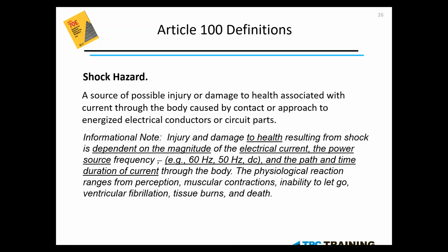Now, shock hazard, other than arc being the heat hazard, now we have the shock hazard, is a source of possible injury or damage to health associated with current that flows through the body by either contact or approach to energized electrical conductors or circuit parts. This is a very serious subject. More times than not, when people think of 70E or electrical safety, they think of the flashes and the blasts because they are visually out there, but 98% of all fatalities come from the shock hazard. So we need to also stress the point of keeping our bodies protected by insulating and isolating using rubber goods.